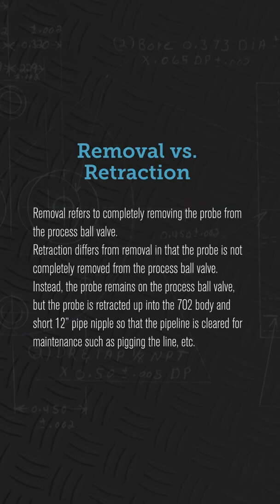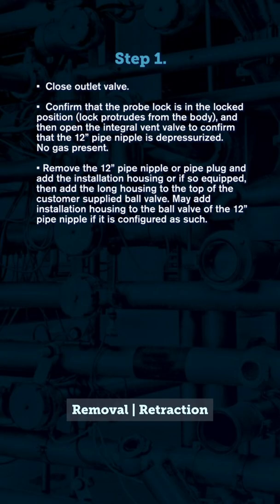Removal vs. Retraction: Removal refers to completely removing the probe from the process ball valve. Retraction differs from removal in that the probe is not completely removed from the process ball valve. Instead, the probe remains on the process ball valve but is retracted up into the 702 body and a short 12-inch pipe nipple, so that the pipeline is cleared for maintenance such as pigging the line.